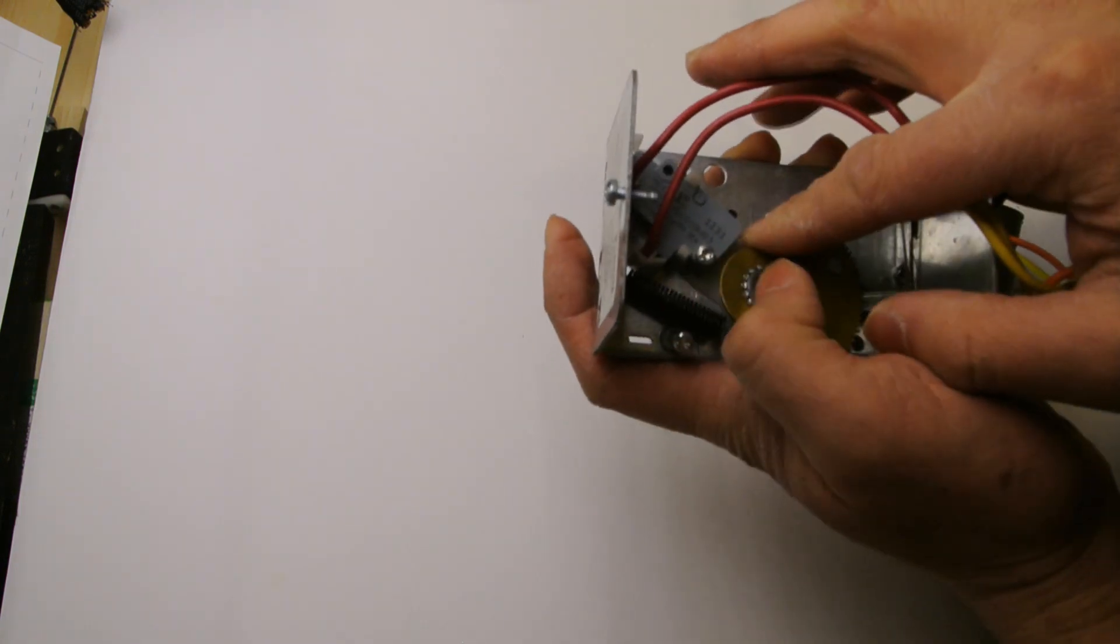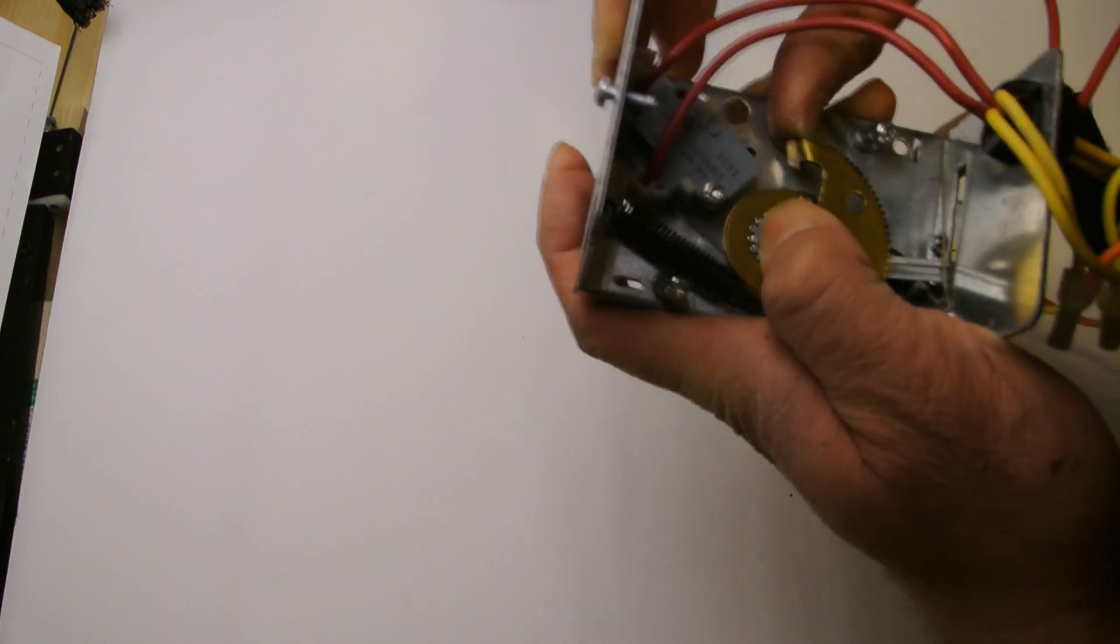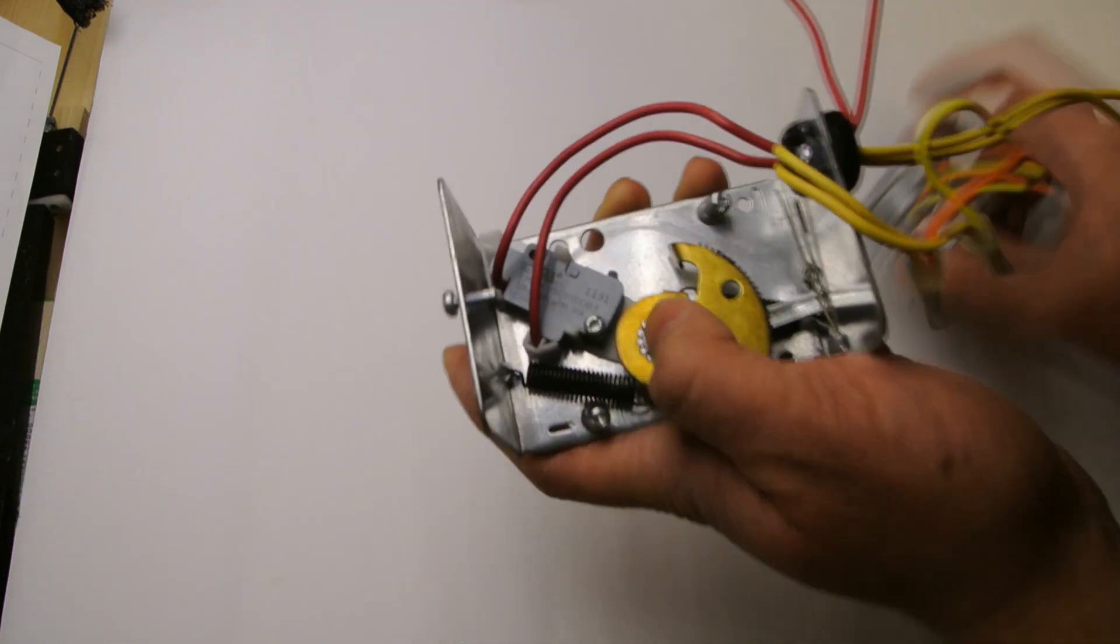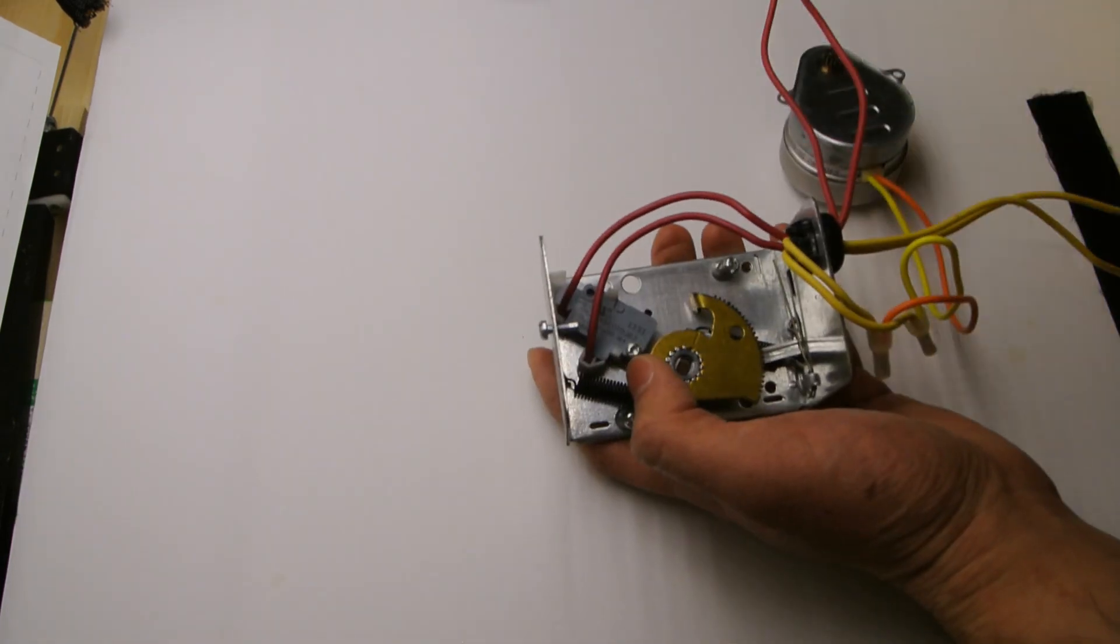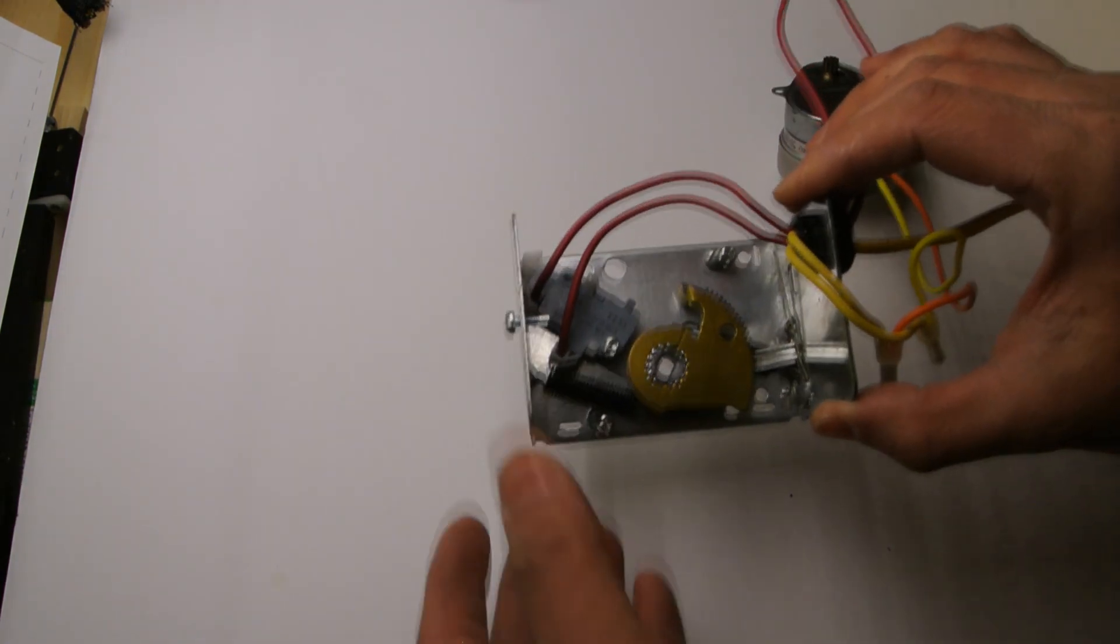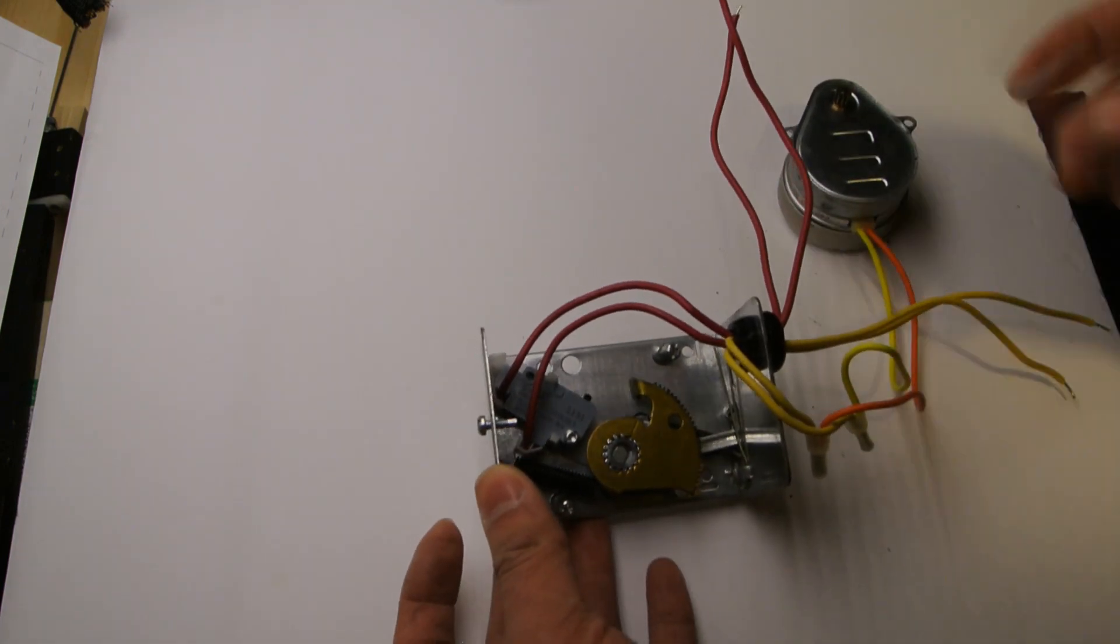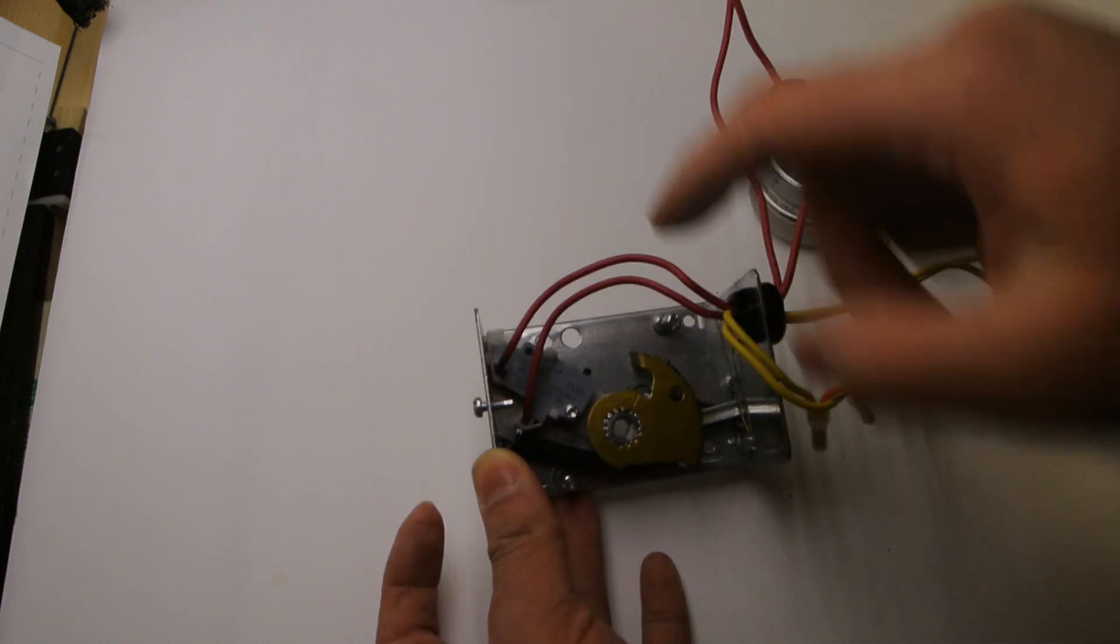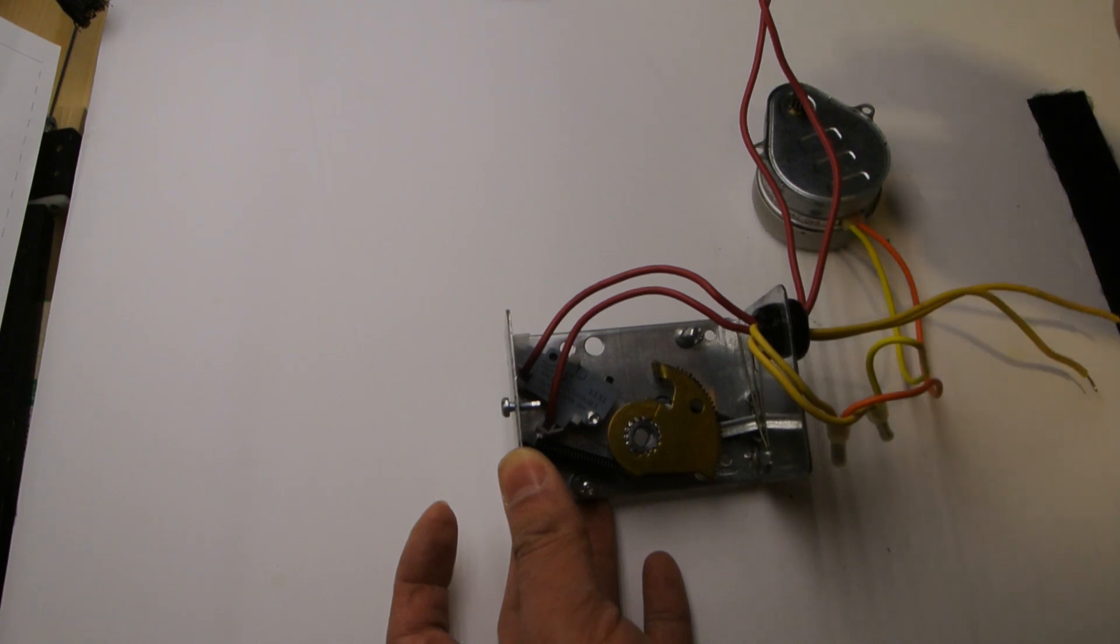So just keep that in mind in terms of troubleshooting as well. It could be the end switch, it could be something mechanical, or it could be something electrical. That's essentially how a zone valve works. Hopefully I didn't confuse anyone and hopefully I was clear in the explanation. So three parts to it: electrical, mechanical with the valve, and then the end switch, which is electrical again.